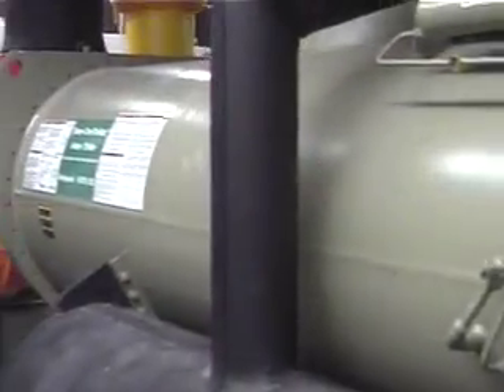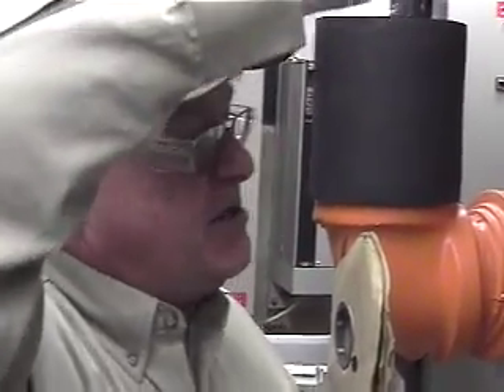This is your condenser right here that we were talking about. Up here is where your discharge line goes into your compressor, or goes into your condenser from the compressor. The little plate that's right here along here. And then you've got tubes the length of the chiller. What happens is a hot discharge refrigerant hits these tubes and condenses down into the bottom of your condenser. At the bottom of your condenser, you see this little leg right here? That's your liquid refrigerant. It's a high pressure liquid refrigerant at this time.